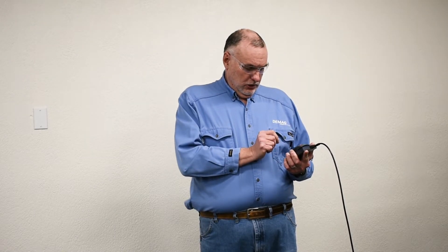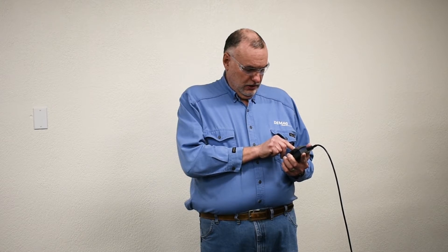So we need to change in the value menu with the keypad to get to value 310. I press escape and enter, then change the value from 241 with the arrow keys, counting up to 310, which is the latest error code that occurred.